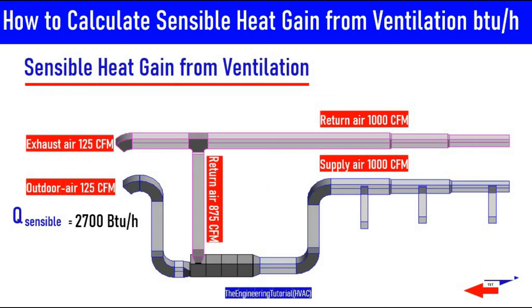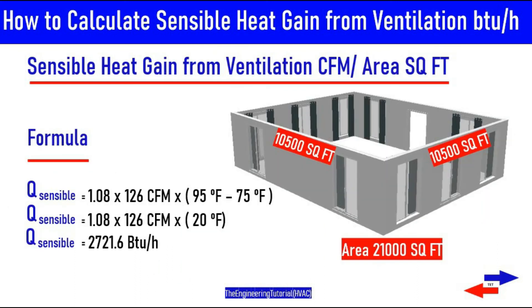The 2,700 BTUs per hour represents the heat gain from ventilation that must be cooled and dehumidified before delivery to the space. Importantly, this is a coil load, not a space load. All sensible loads can be a coil load, but not all coil loads are sensible space loads. The cooling of ventilation outdoor air is a coil load, not a sensible space load.